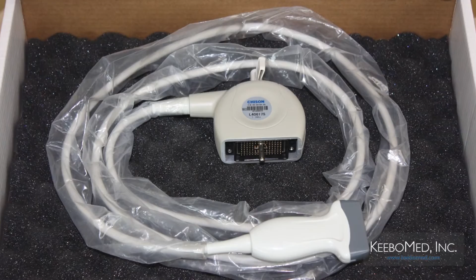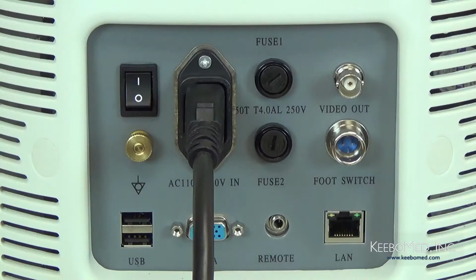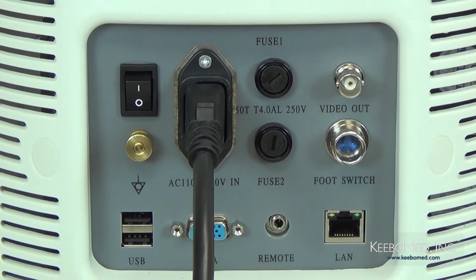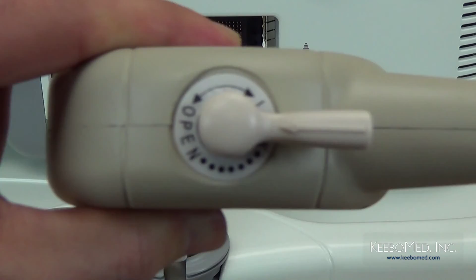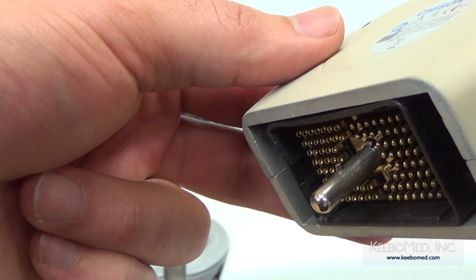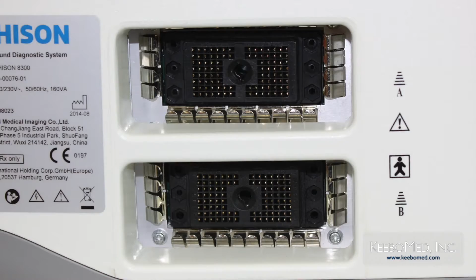Now we're going to consider the proper installation procedure of the probes. Remember, it's important to only use the probes that are provided by the manufacturer for the 8300. The first step is to make sure that the unit is turned off. Step 2. Open the probe box and carefully check the probe lens, the cable, and the connector to make sure that it is in proper working condition. Step number 3. Put the probe lock knob to open status and make sure that the small tongue of the probe lock inside the probe connector is at the same position of the slot on the probe socket.